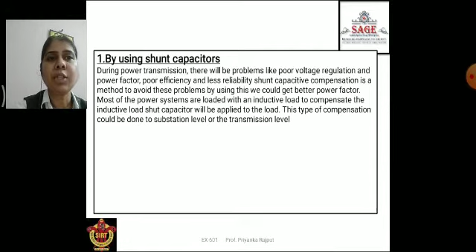Most of the power systems are loaded with inductive load. To compensate the inductive load, a shunt capacitor is applied to the load. This type of compensation can be done at the substation level or transmission level. Now the advantages of shunt capacitor compensation are as follows.